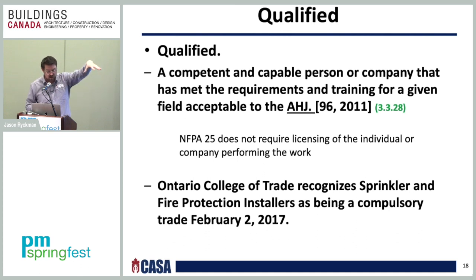So in our province of Ontario, there is a requirement of licensing. If you haven't heard that, ultimately any person inspecting, testing, or maintaining a system has to be licensed through the Ontario College of Trades, which recognizes sprinkler protection installers as a compulsory trade. It's the same as being a plumber or electrician. It came into effect February 2nd of 2017. There's no requirement, however, for a contractor. Obviously, being biased, being CASA, we prefer to have a CASA member doing your inspection, testing, and maintenance. So just make sure you're aware of that.